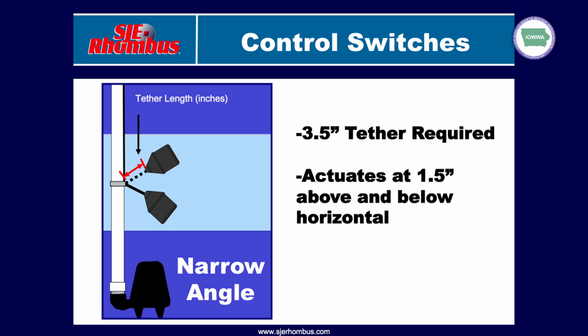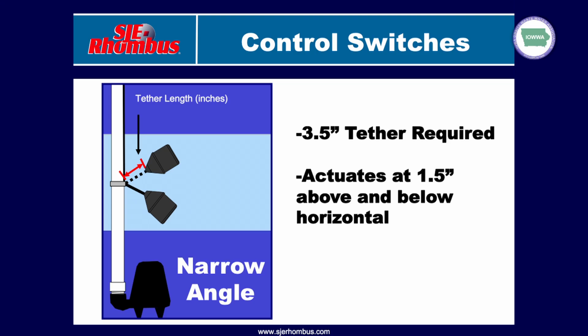All right. Talking about control switches, as we already mentioned, we're not going to carry any load with a control switch. It's going to be used to actuate a relay for a high level or low level alarm, or a control panel where we're going to use a coil to energize or de-energize a motor contactor for turning pumps on and off. With a narrow angle switch, we're going to have a little bit different setup. With the control switch, we want to have at least 3.5 inches of tether, but we don't need any more than that. The longer the tether out from the pipe or from the float tree, the greater the chance it's going to hang up on something.